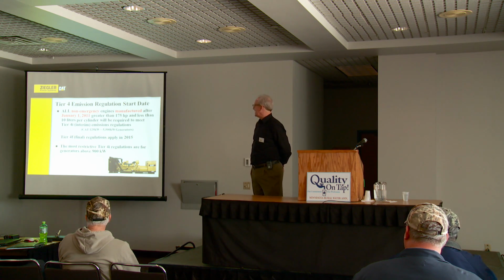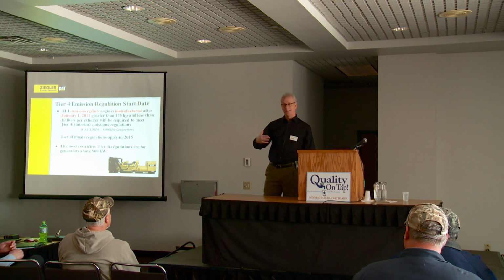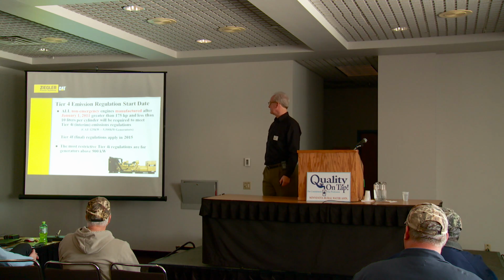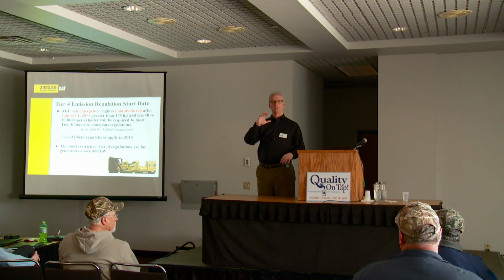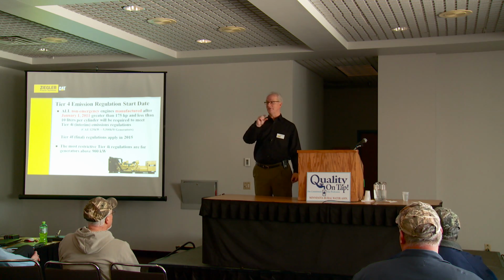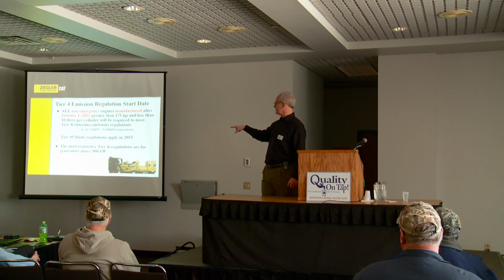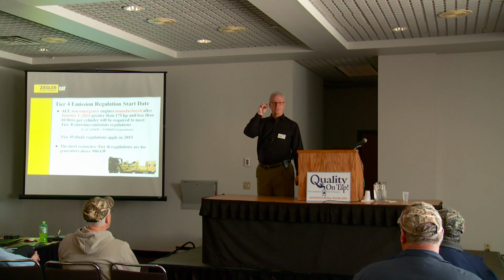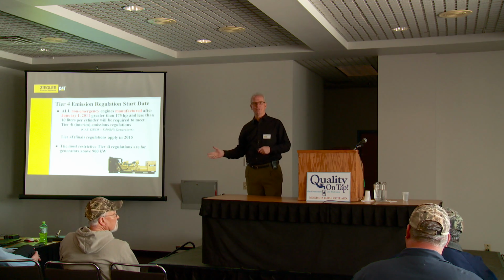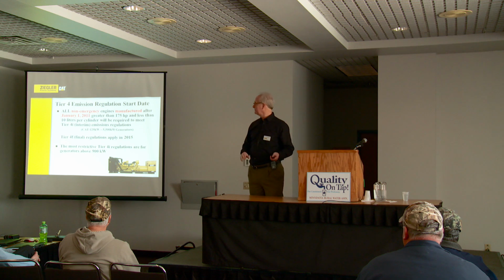So there are additional rules that are coming on in 2015 that tighten these things down even further. And as I said before, there's a lot of different specific emission levels for the different sized engines. And it just happens that for whatever reason, generators greater than 900 kW are the place where the emission levels are the smallest at this current level. So you'll find that if you need a bigger engine, it's got more emission control stuff on than if you needed an 800 kW engine today.